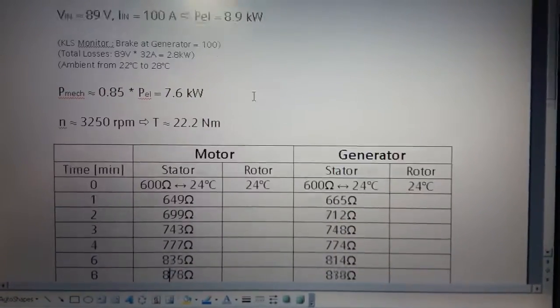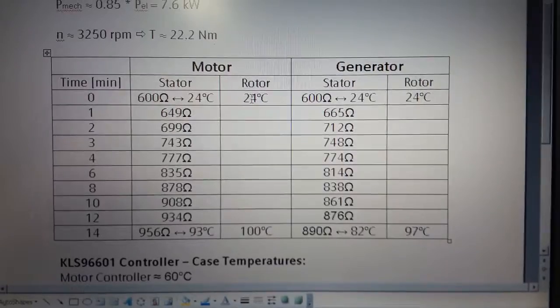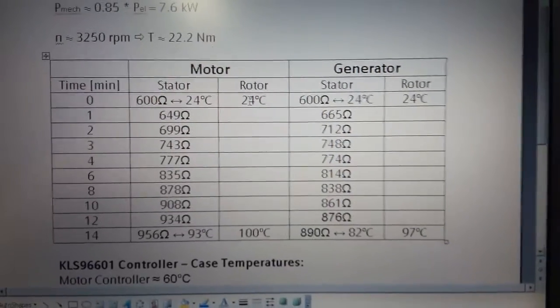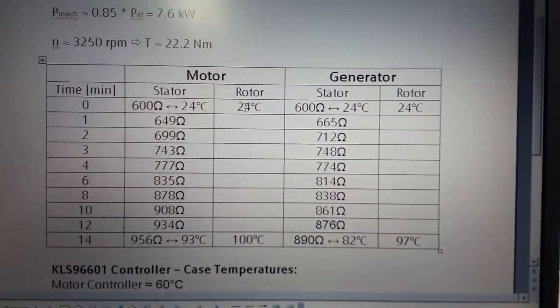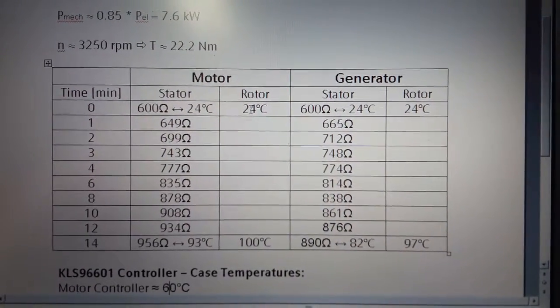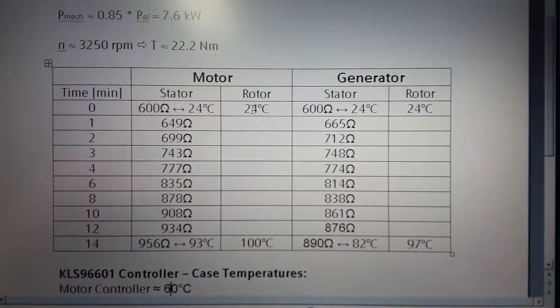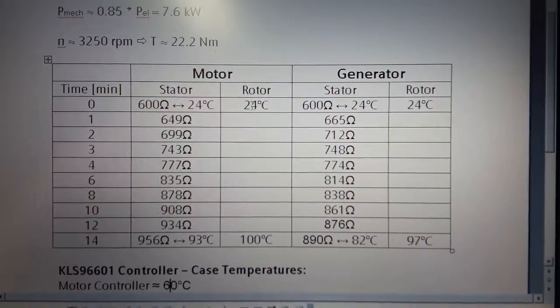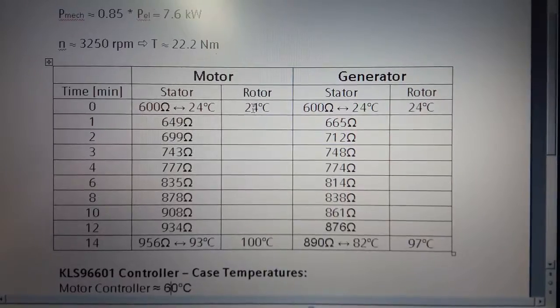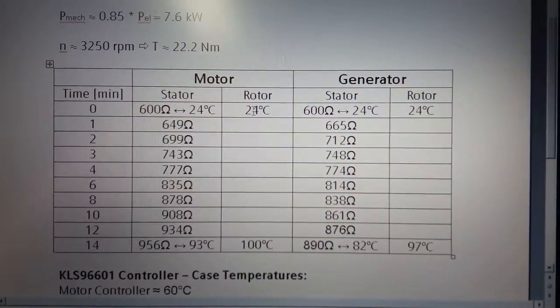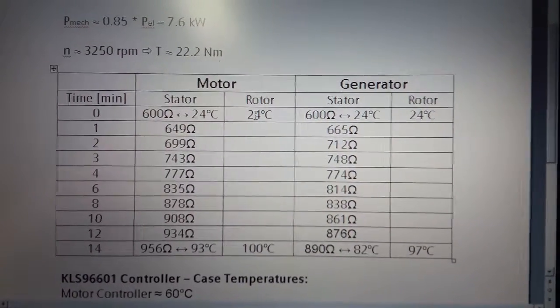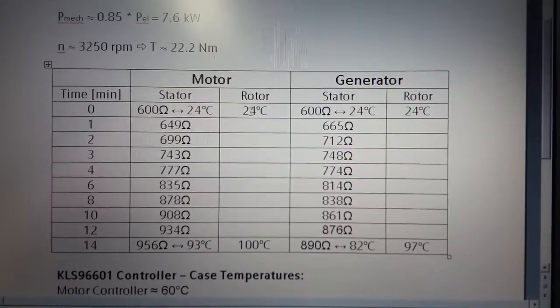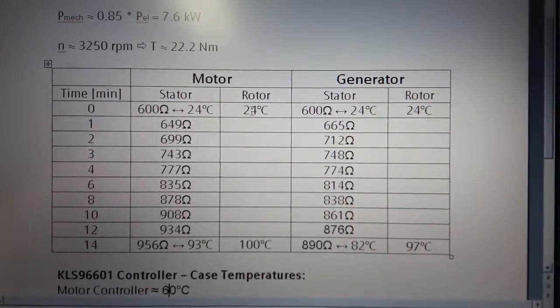Now you can see how the temperature increased. The motor was on a higher temperature level than the generator. Both started at 24 degrees Celsius. The motor ended up at 93 degrees Celsius stator temperature and the generator at 82 degrees Celsius.